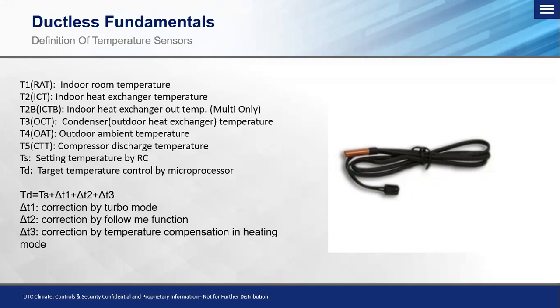The rules of this turbo mode are when it is hit, you'll see on a unit that has a digital screen or a readout, you'll see on there to indicate to you as a visual indicator that this mode is active. If you do not have a digital display, all you're going to hear to confirm that this is in turbo mode is an audible beep. When it runs in turbo mode, it has 30 minutes to try to get to the set point that you have for turbo mode. Now, when you hit turbo mode and then you pick, let's just say 65, it has 30 minutes to get that space to 65 degrees, and it's going to run at full modulation to do so. Essentially, it's trying to get to set point as quickly as possible. That is what our turbo mode is capable of and what the main purpose of the turbo mode is.